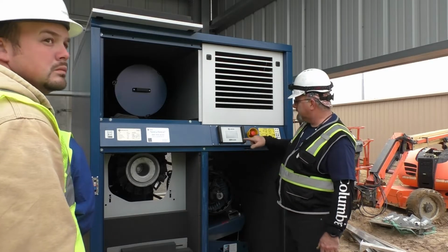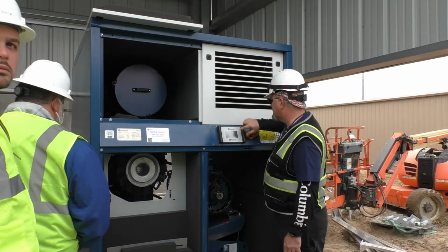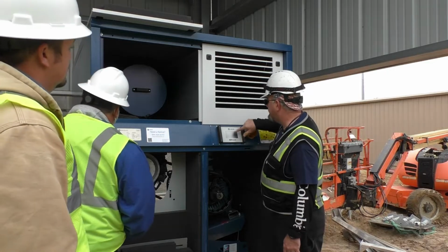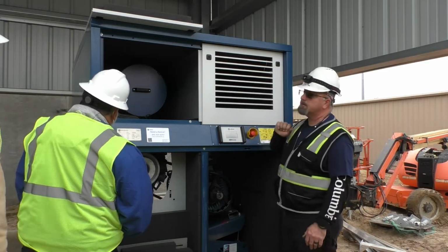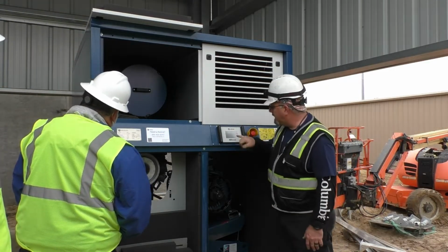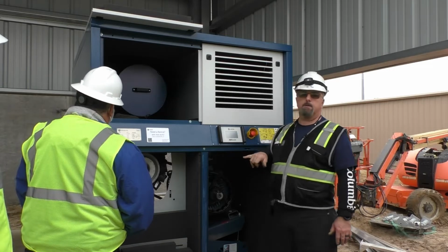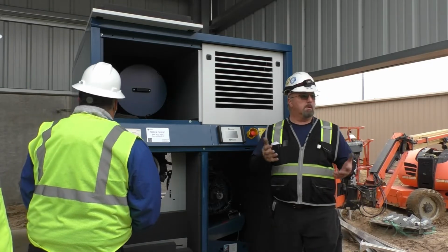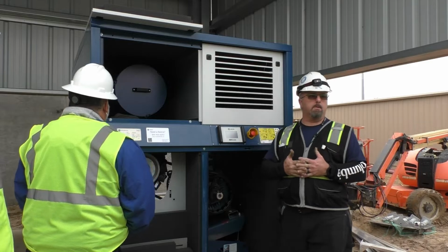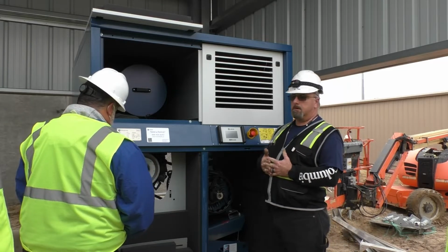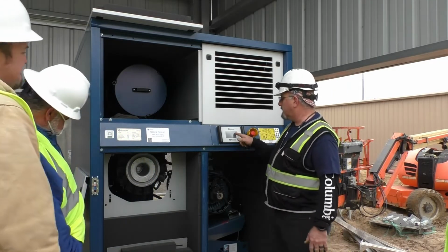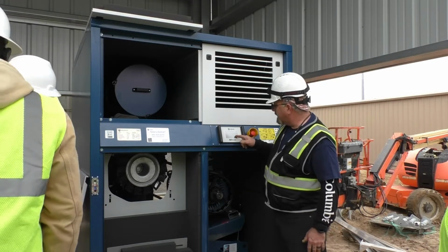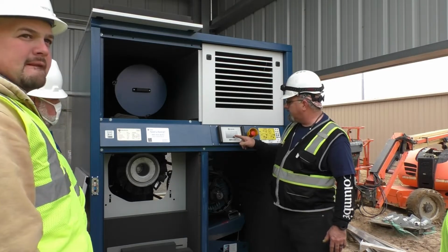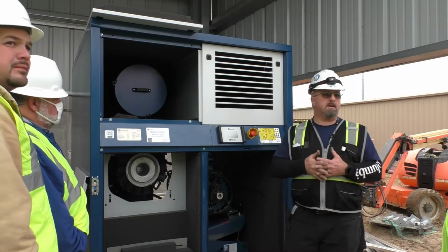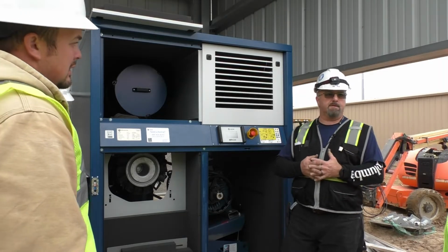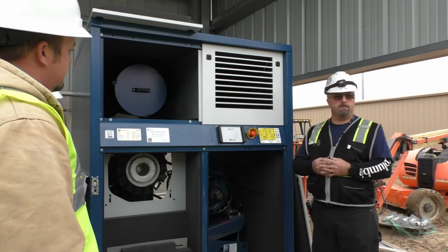You may have to actually go into the control system and go under the miscellaneous to actually set it up, and we would walk you through doing that over the phone. The third one down is remote on off. You change that to digital because it's receiving a signal from the drive.